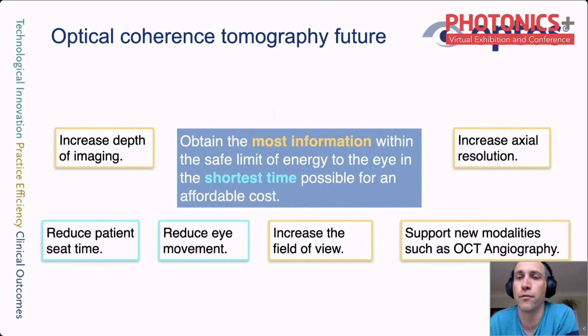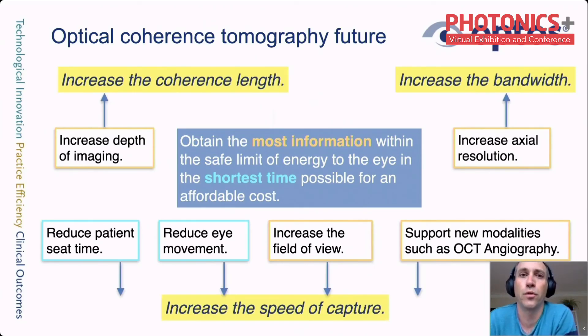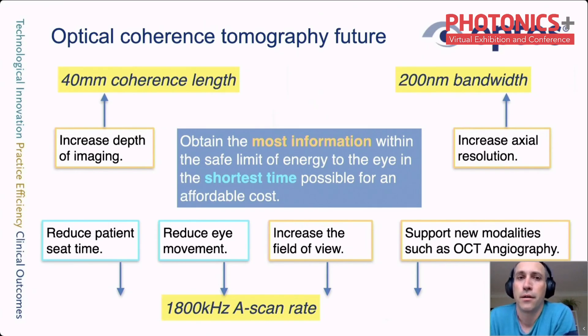Another challenge in ophthalmic imaging is eye movement — a problem at different levels, from small saccades in tens of milliseconds to large eye movements such as drifting in the order of hundreds of milliseconds. Short captures are important also for reducing the time required per patient. Important photonics trends for OCT include increases in speed of capture, bandwidth, and coherence length. The cost of combined components needed to achieve performance targets is currently too high for viable commercial products, so the real challenge is achieving these targets within reasonable cost and size.